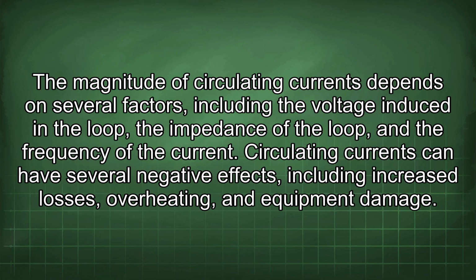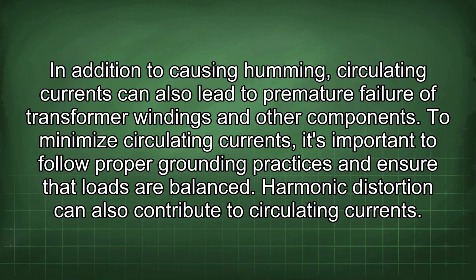Circulating currents can have several negative effects, including increased losses, overheating, and equipment damage. In addition to causing humming, circulating currents can also lead to premature failure of transformer windings and other components. To minimize circulating currents, it's important to follow proper grounding practices and ensure that loads are balanced. Harmonic distortion can also contribute to circulating currents.